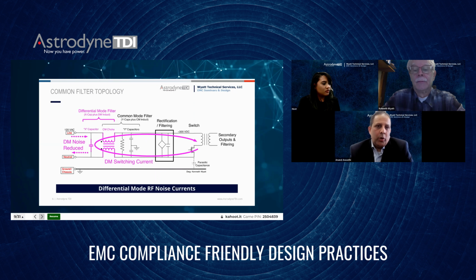And you pointed out about common mode, and that's a great point. The two windings of a common mode coil are never identical, and there is a percentage of difference between them, and that becomes a differential mode inductance, which helps with the differential mode noise. But there are a couple of applications we work with, typically MIL 461 and the lighting application, where the compliance requirement goes down to 9 kilohertz, which is way below the 150 kilohertz commercial frequency range.